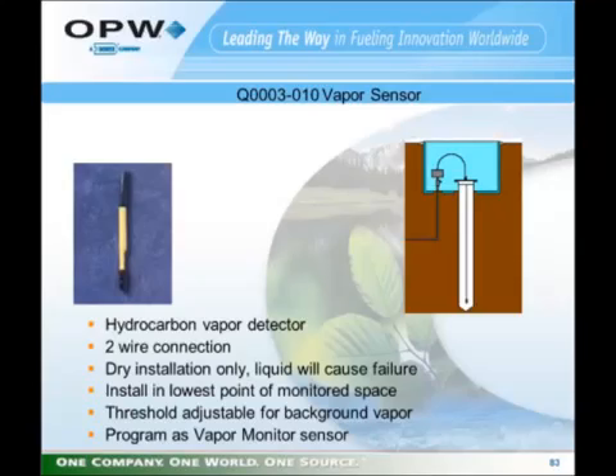The vapor sensor is no longer accepted as a primary source of leak detection or release detection. It is acceptable as a secondary method, but not a primary method. And the reason is that when a vapor sensor is installed on a system, it must be adjusted for any background vapors that may be present. If background vapors are present, that means that something has leaked already. If the vapors do not increase but remain constant, that could mean that there is a leak, but other conditions that prevent the vapor concentration from increasing above the threshold amount. This is programmed as a vapor monitor sensor in the system programming.